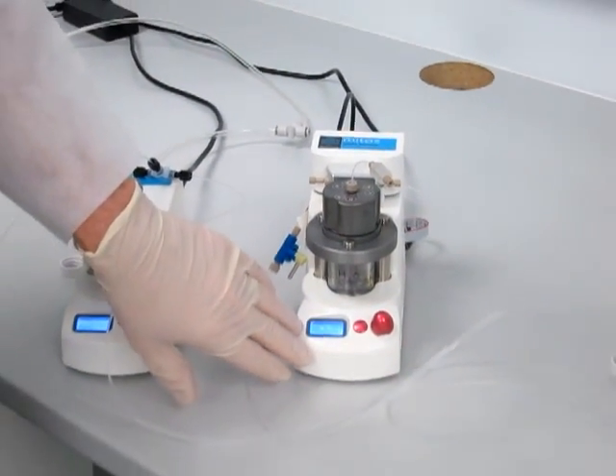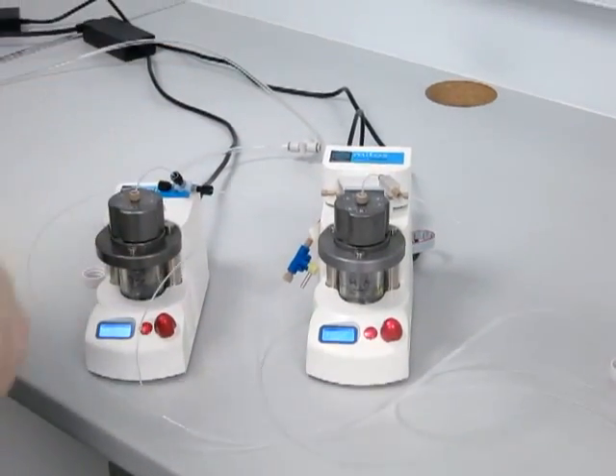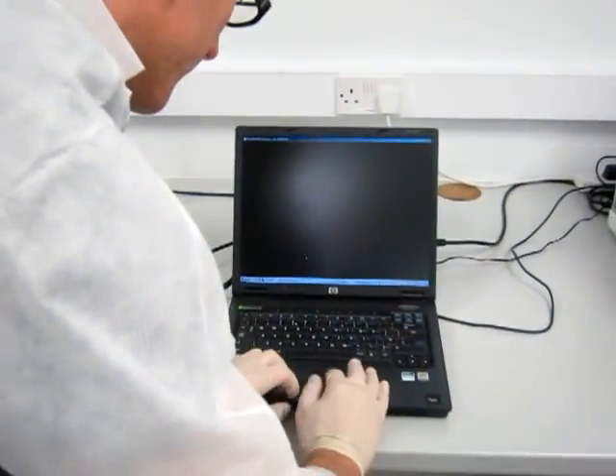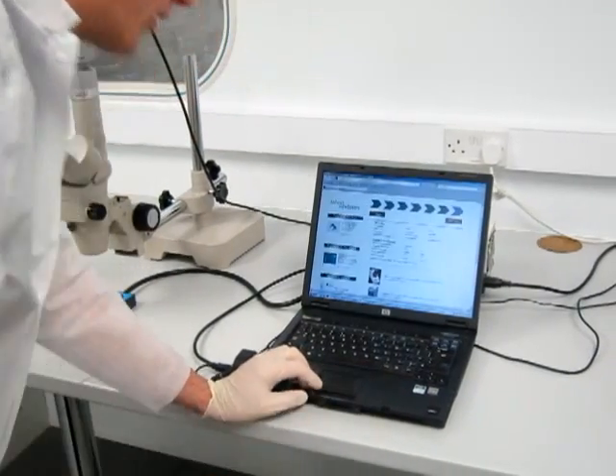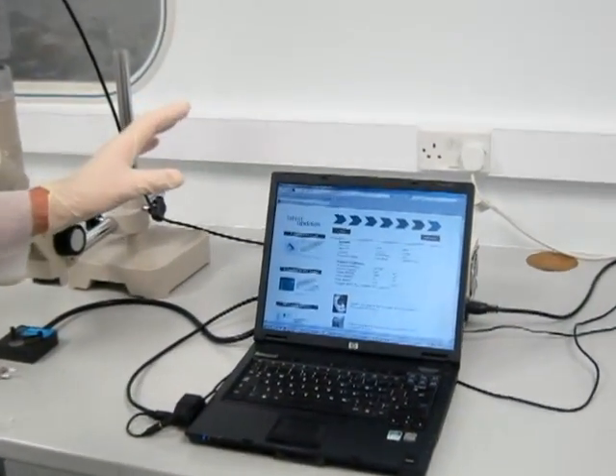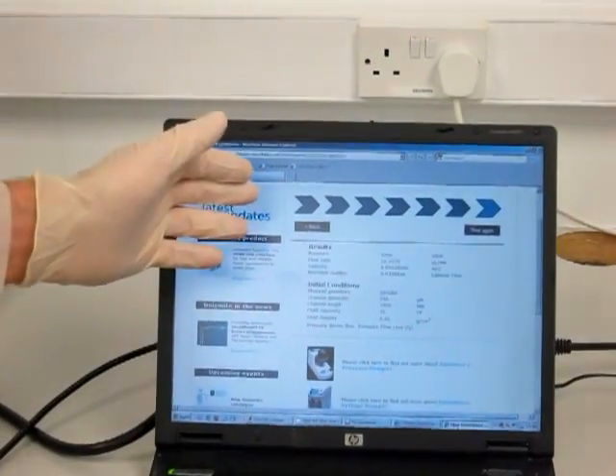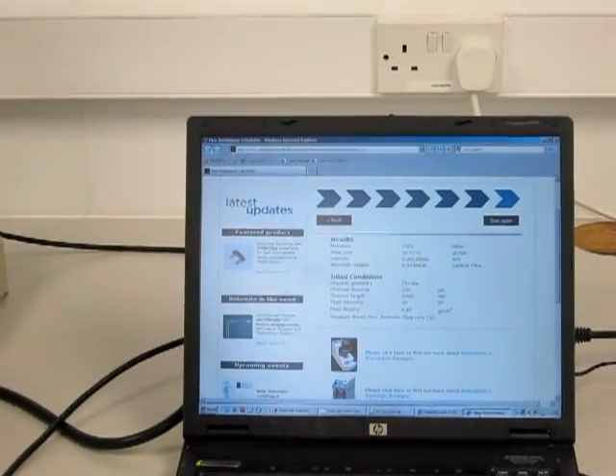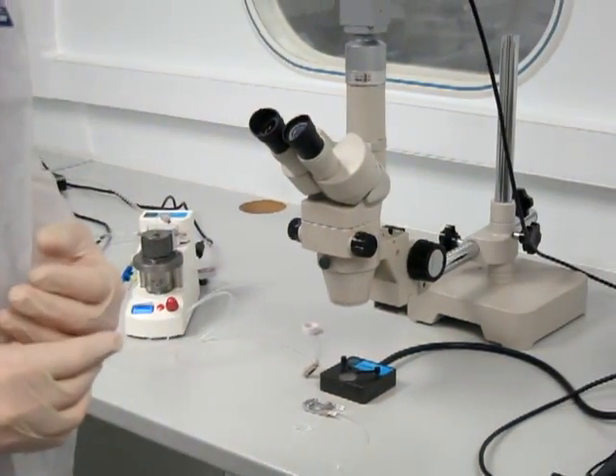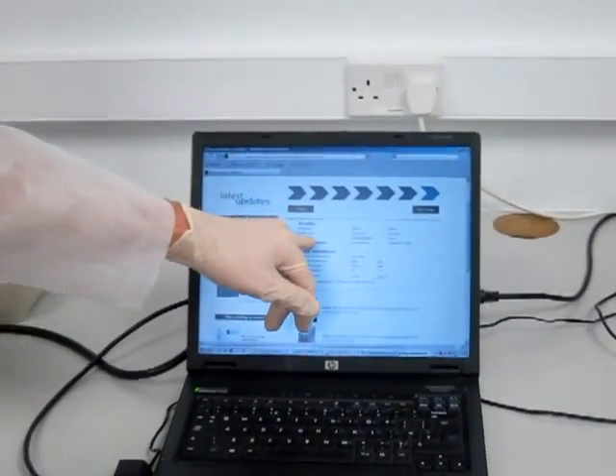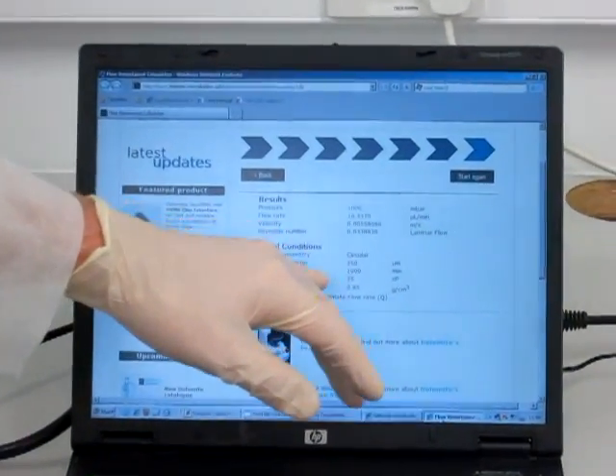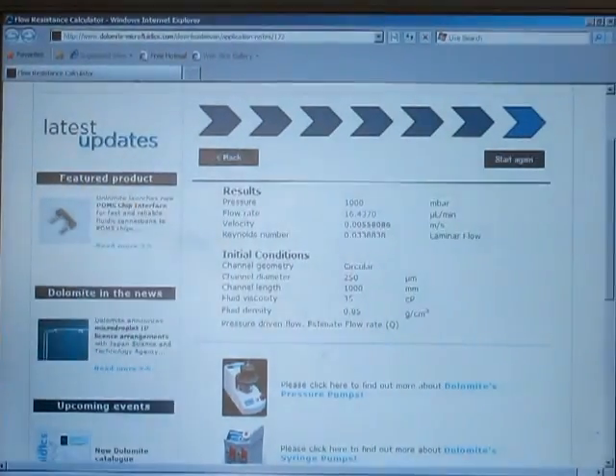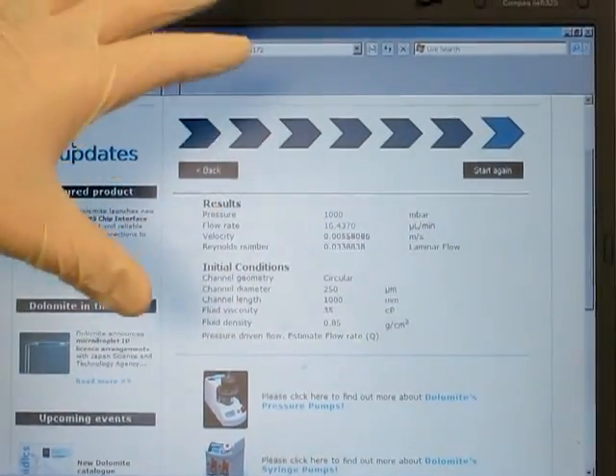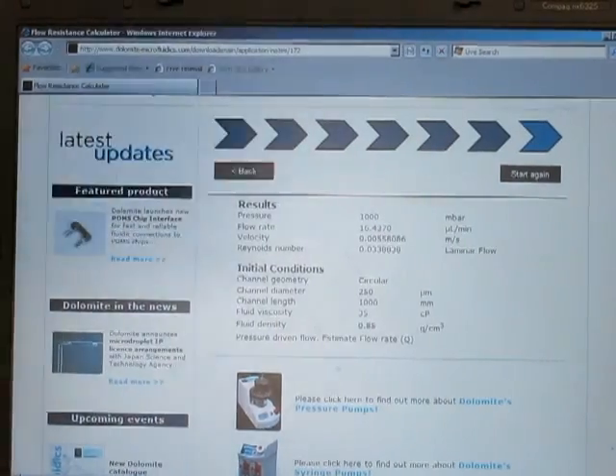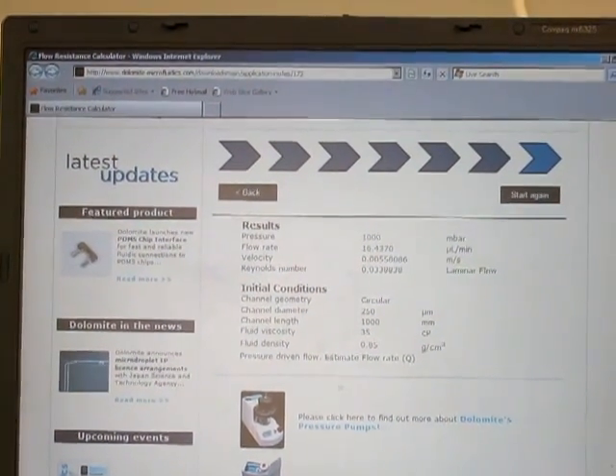So from the front we can set the pressure, and what we can do is, on the Dolomite website there's a flow resistance calculator. Essentially, if we're using a custom flow resistor kit, which we use in this case, using 0.1mm internal diameter pipe, we can put in the length of pipe, the ID and the pressure, and it will tell us what flow rate we'll expect to get. We also put in fluid viscosities, but some of those are listed on that calculator. So that tells you roughly what flow rate you'd expect to get using this calculator.